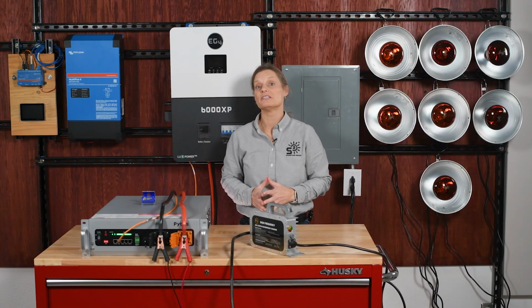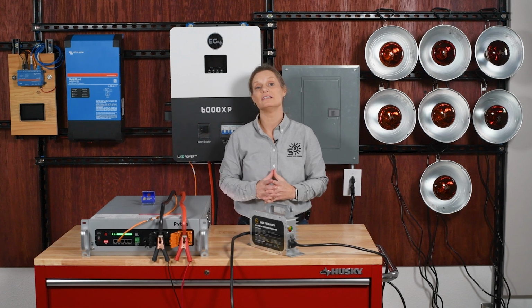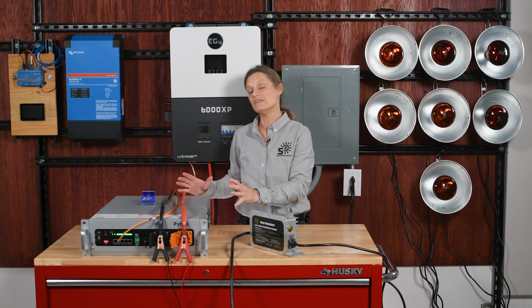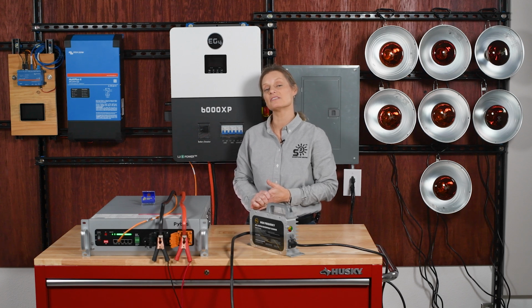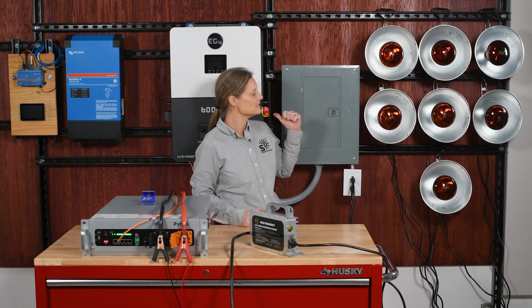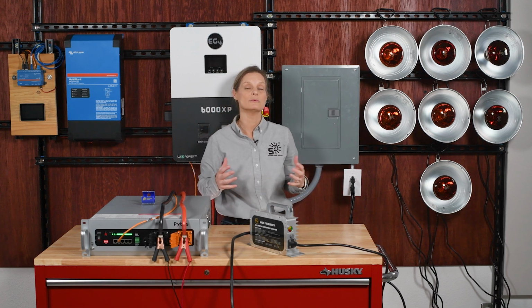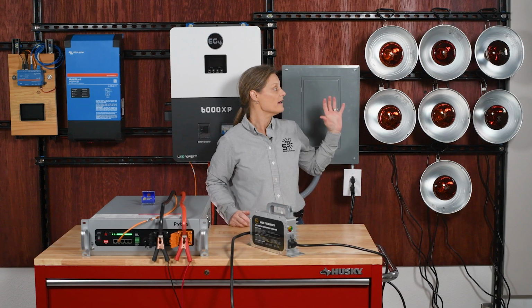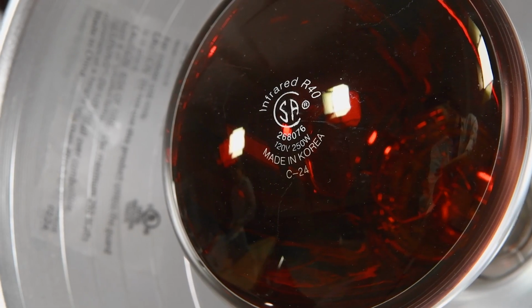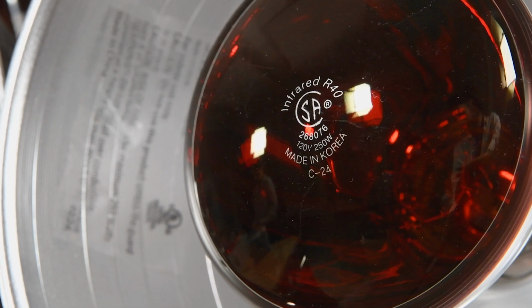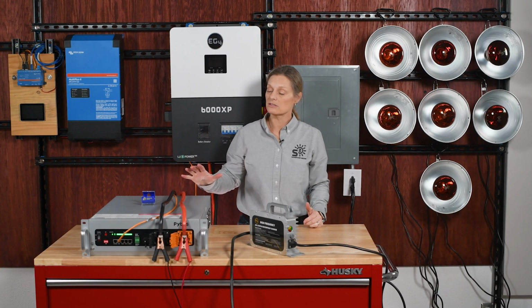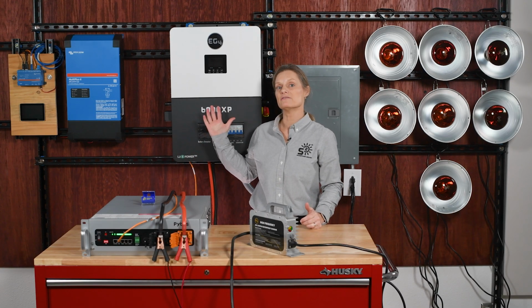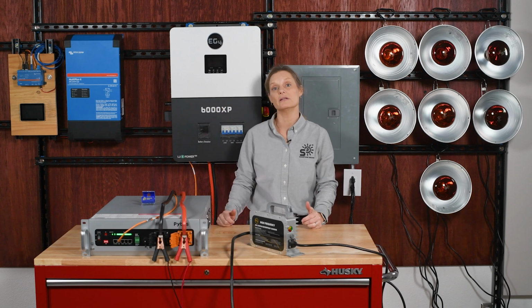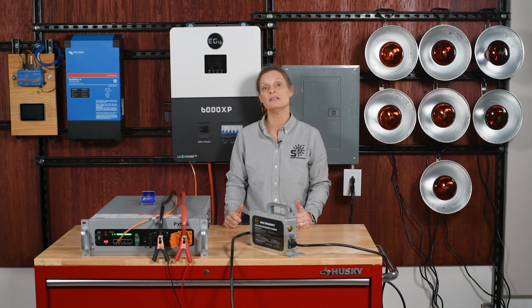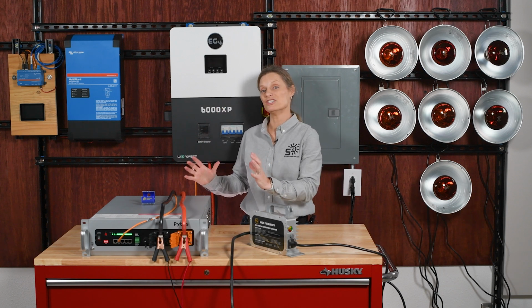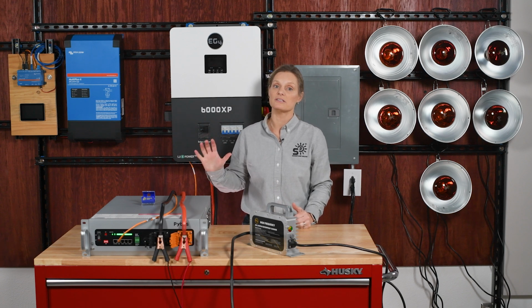Now let's run a discharge test to measure how the V5 handles a continuous load. We've already connected the V5 battery to the EG4 6000 XP, so we went ahead and connected a panel box with an outlet so that we could run this load test. We have 7 heat lamps, each with 250 watt bulbs to run this load test. We're gonna go ahead and turn the battery on and see how the inverter is reading how much this load is. This will give us an indication of an estimation of how long it should take to discharge this battery.